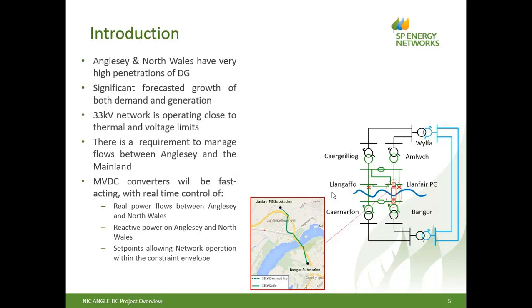And you can see on the diagram that we have alongside there that the squiggly line between Llangaffo and Caernarfon and Llanfair PG and Bangor is the Menai Straits, as illustrated there. And we currently have two connections across to Anglesey from the mainland at 33 kV. And then the only other connection is the 400 kV, which is the pale blue that you can see between Bangor and Wylfa. What this means is that obviously we'd like the power flows to go through the 400, but because we run a meshed network in SP Manweb, we do have this parallel path for the 33. So what we end up having is quite an amount of power flowing across the 33 network.